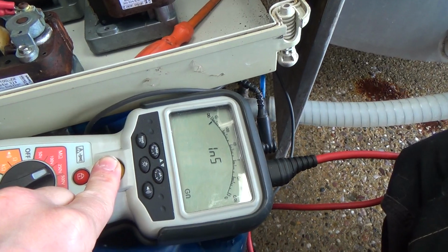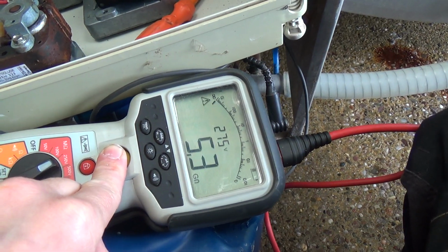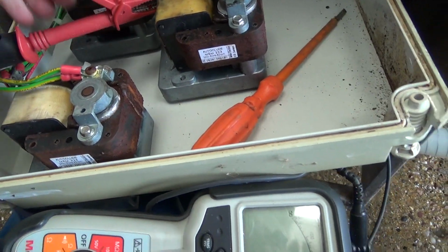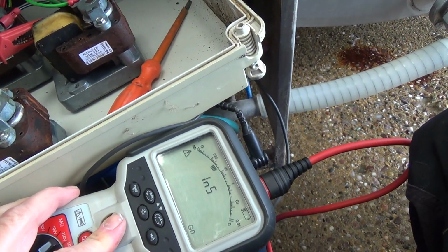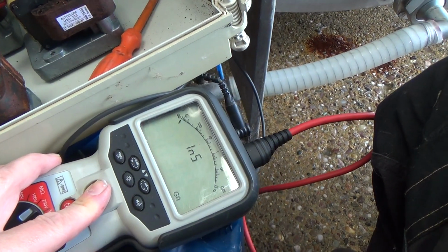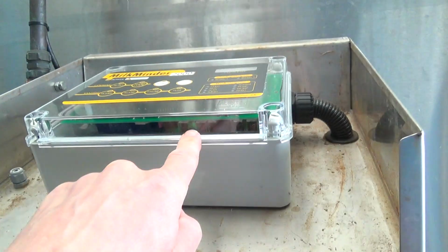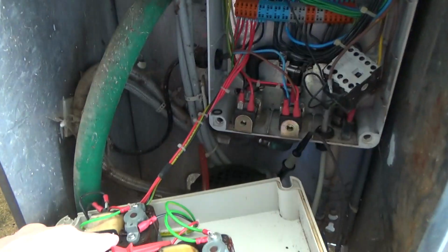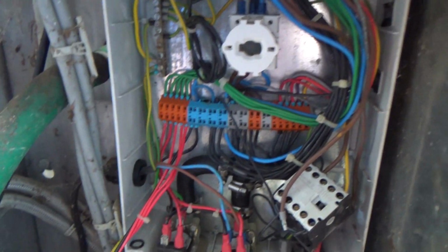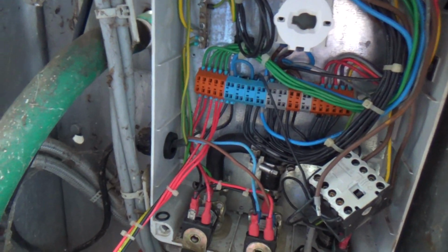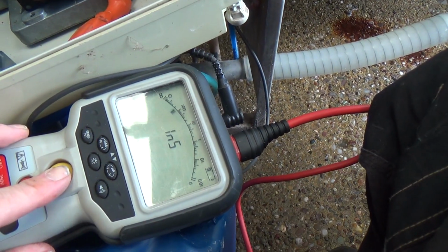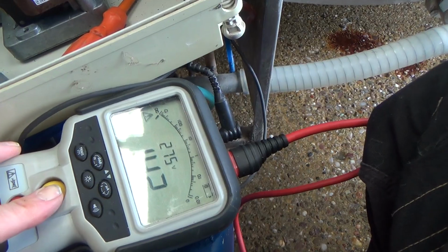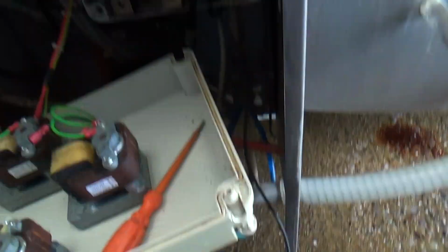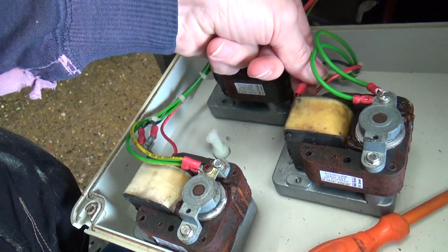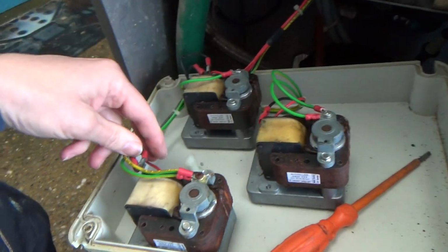We're on the chemical pumps, gigaohms. We've just pulled the neutral connections off because the live wire should just go up to one of the relays in that box, so the live wire should just go up to one of these and then off. So it's probably, unless one of the wires or these connections are shorted out, that disconnects that lot. So they're looking all good. Let's put them back on.